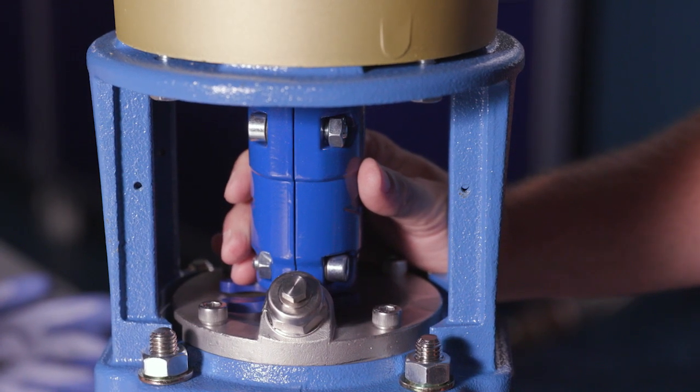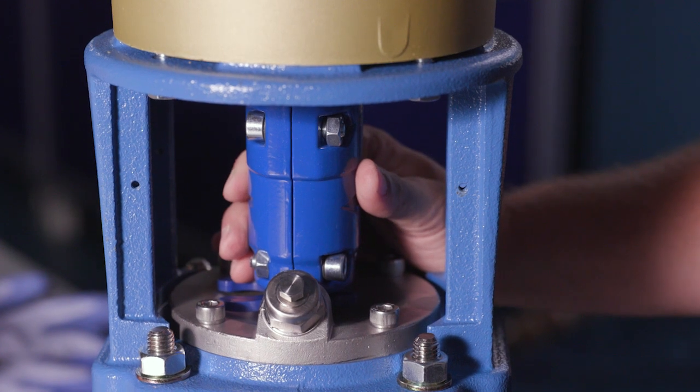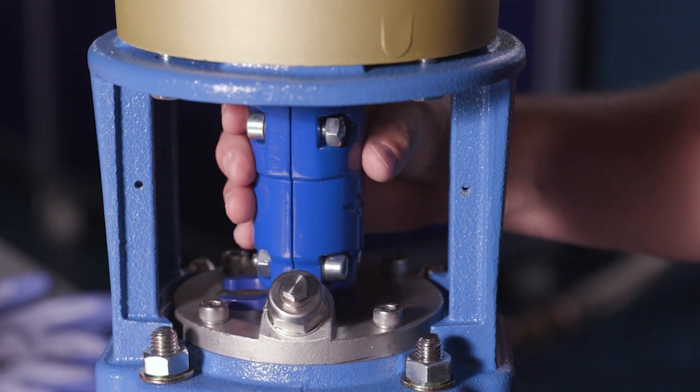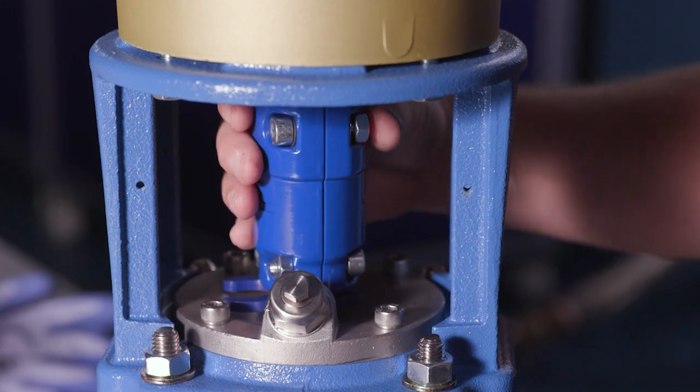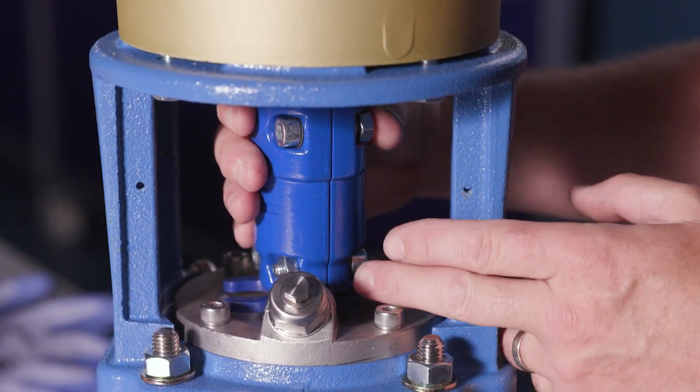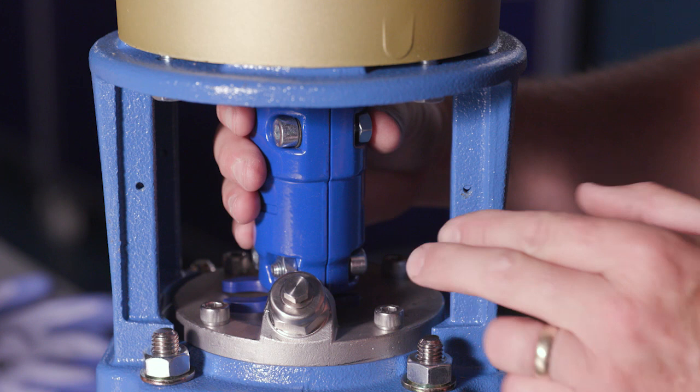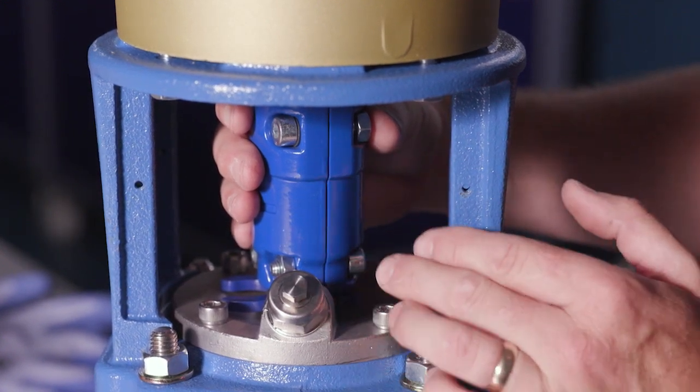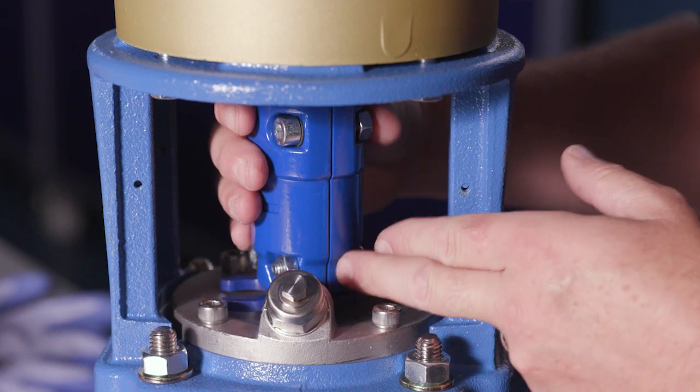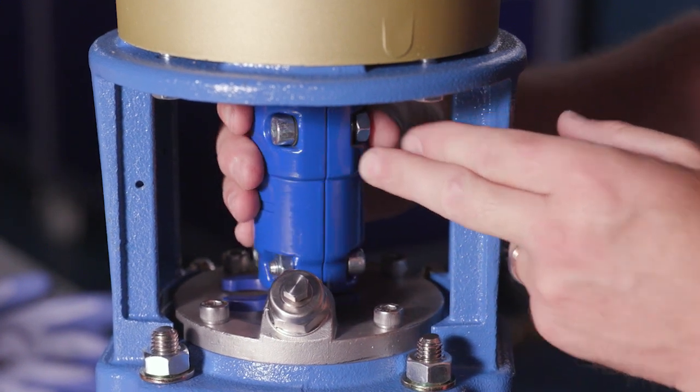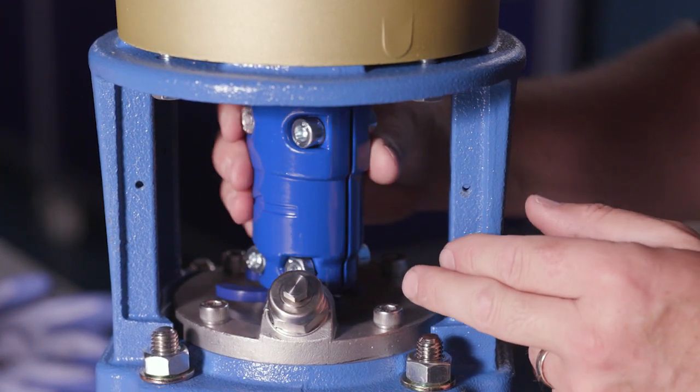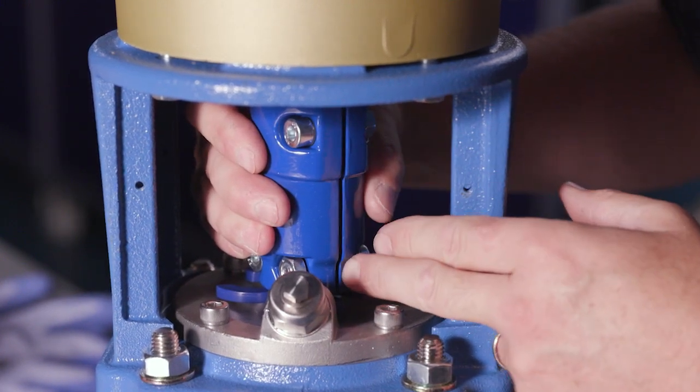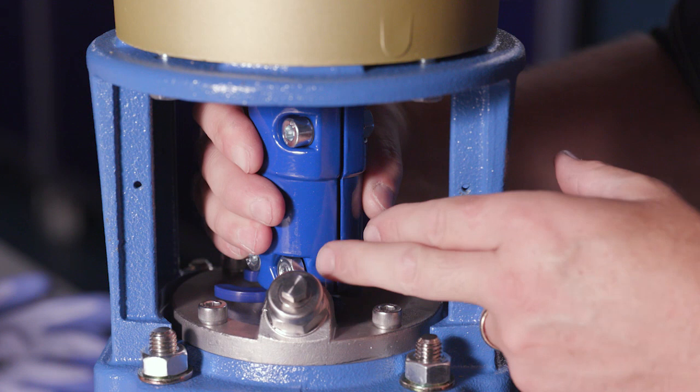Now that we've got the shim all the way in, we've set the stack height properly. In other words, those impellers have been raised just enough so that we got proper clearance. Now really the next step is you want to make sure that you tighten the coupling evenly, not only top to bottom but side to side.